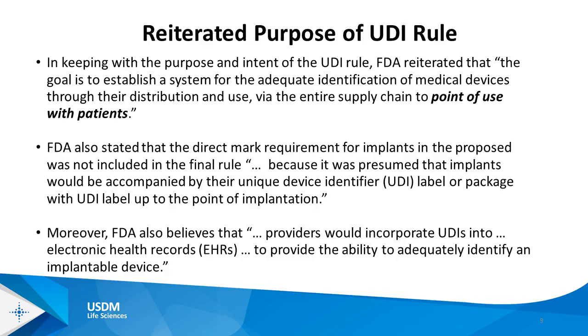I think most important in the letter, and this has been maybe a point of confusion, is that FDA reiterated the purpose of the UDI rule as it relates to implants and as it relates to this issue, and goes back to some of my initial slides, but that the goal really is to identify a device up to and including the point of use with patients. So this is not just a supply chain issue.